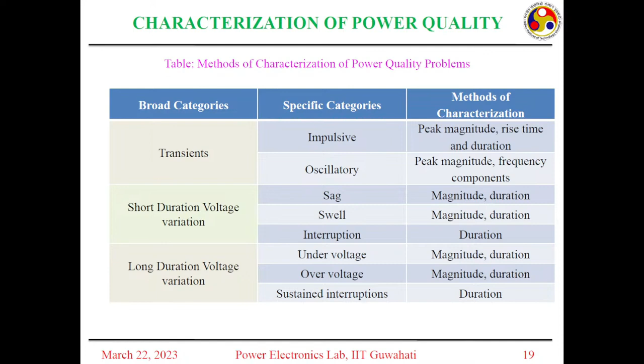And we have voltage imbalance. Voltage imbalance is characterized by symmetrical components: positive sequence, negative sequence and zero sequence components. Waveform distortion is characterized by total harmonic distortion and the harmonic spectrum, like what types of harmonics are in the waveform. Voltage flicker is characterized by frequency of occurrence and modulating frequency.